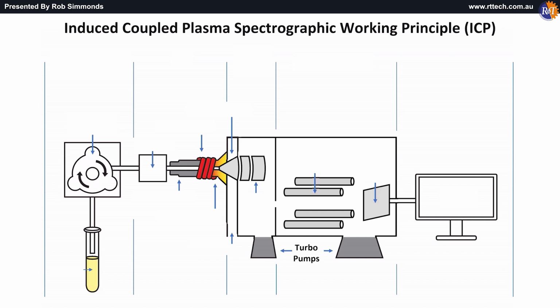Inductively coupled plasma spectrographic working principle, ICP. The ICP spectrographic analysis works by, first, system sample introduction. A robot sampler picks up the sample from a test tube. There could be 100 samples in the grid. A peristaltic pump moves it through the nebulizer in the ICP system.